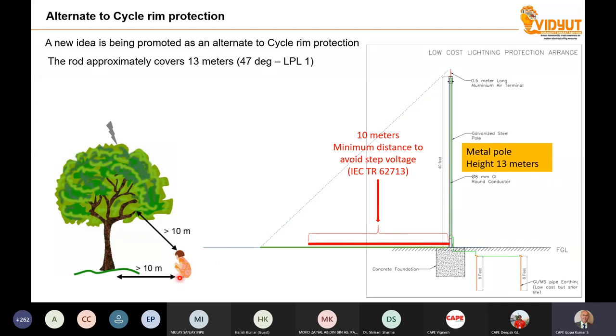Now, the IEC 62713 says in case of a lightning strike in some kind of an object, you have to be 10 meters away from the tree, for example. Now you have a rod, and if you wanted to be safer, first you have to be 10 meters away from this particular pole. So first 10 meters is gone. Consider the earthing system is an MS pipe, and it corrodes after some time. Now at the edge, the last place, because of the height of the person, of course, there is a chance of a direct lightning strike. So you cannot go to the edge. Then finally, you get a protected area, which is about 1.5 meter.